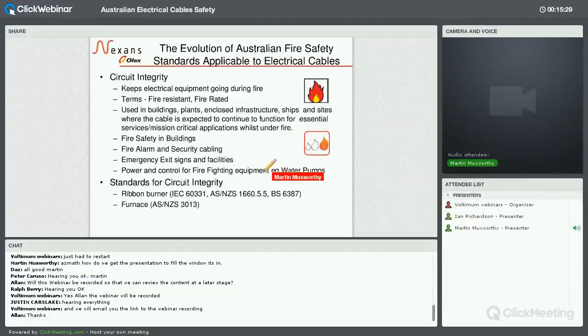In talking about circuit integrity cables and standards, there are two essential or fundamental types of standards used to describe and test the circuit integrity performance of cables. One is what we call a ribbon burner test, and these are the IEC 60331 series, the 1660 Australian Standard Part 5, and there's many more standards like these, but these are the principal ones that are used around the world. As opposed to the furnace standard test, the furnace standard test is described in the AS3013. And we'll look at each of those in a bit more detail in a moment, and hopefully the differences will become fairly obvious.